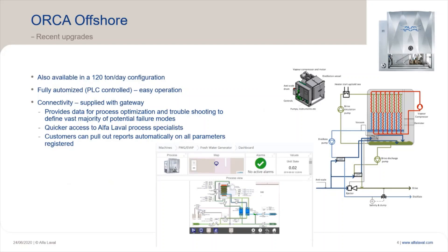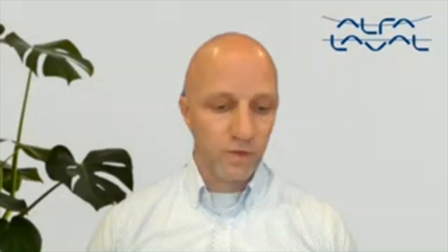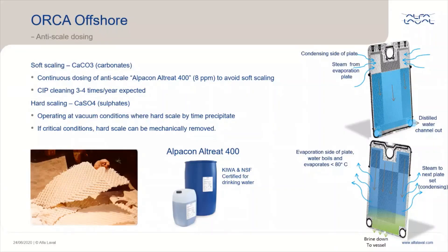My colleague Peter will continue to show you how to ensure uptime. Thanks, Luciana. Let's first look at anti-scale dosing. An anti-scale or scale inhibitor agent is a pre-treatment chemical injected into the feed water before it enters a freshwater generator. Its presence delays the reaction between calcium, magnesium, and bicarbonate. Scale formation is significantly reduced as the water is being distilled, and precipitation settling and baking onto the heat transfer surface is more or less prevented. When processing seawater there is exposure to scaling due to the high salt content, but if operated within design specifications and with correct anti-scale dosing, this is not a major issue.